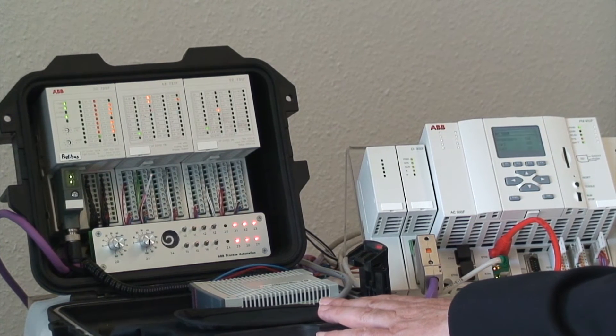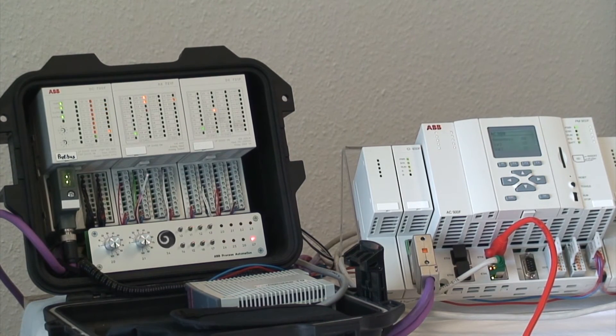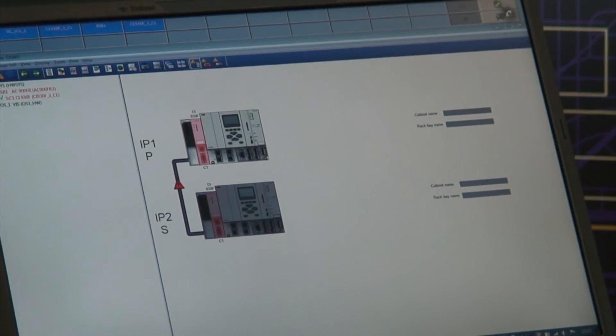But the controller is no longer in sync state, which means the next failure will cause an unplanned trip. On the operator station we see that the Profibus lines are disconnected. What I do now is start connecting the lines again, and after a very short while our operator station shows as healthy again.